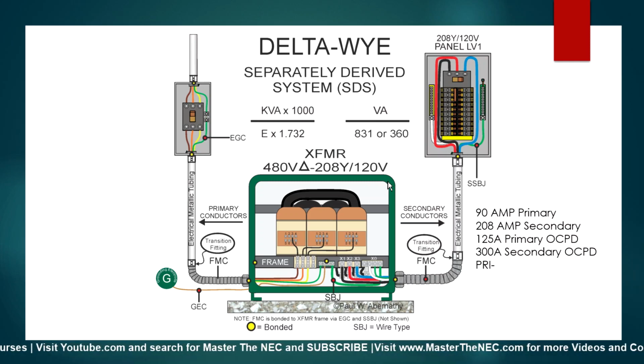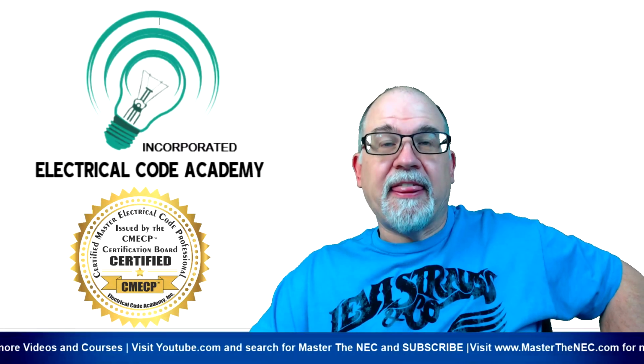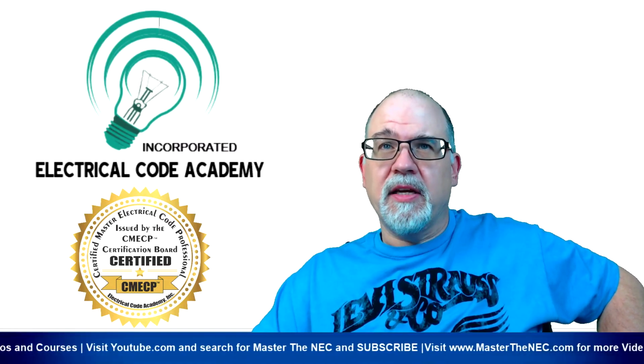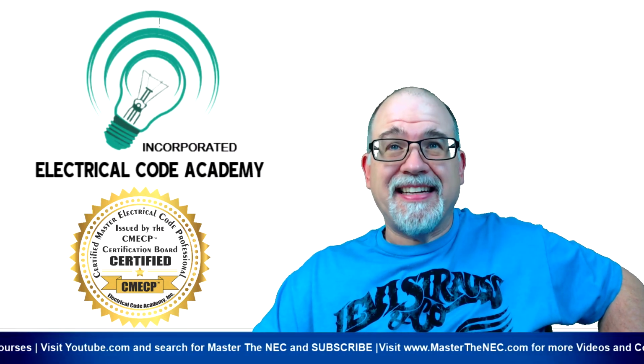So typically what I would probably do, we're not going to do that in our example, but what I would probably do on this transformer to be efficient is I would do this at a 225. And I would size these conductors for 225 amps. And I would make sure my load doesn't exceed 208, but my breaker would be at 225, and that would be perfectly fine as long as I calculated my load. Remember, folks, I could have a 1,000 amp overcurrent device as long as my load doesn't exceed it.